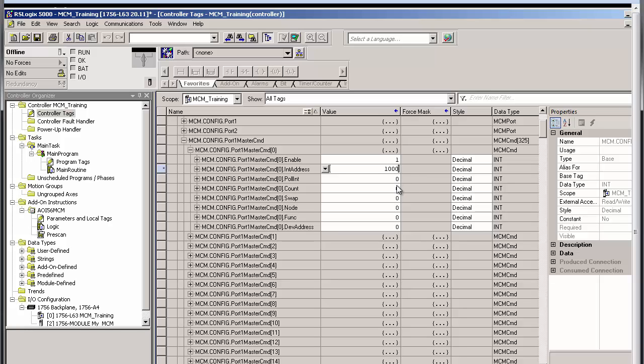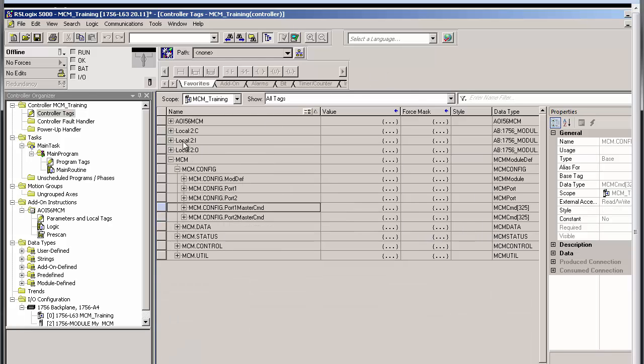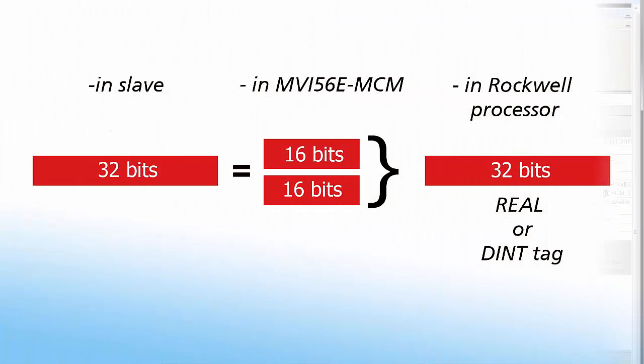Each of the two numbers I'm going to read will be float values, which, due to the limitations of the Modbus protocol, require two 16-bit registers each. So, I'll move down to count and enter 4 as the number of registers I want to use. I'll select node 1 as the device to give the command to. A function code of 3 means to read multiple holding registers. And a device address of 1024 means we'll start reading registers from address 41025 in our power monitor, which is where the values for phase A voltage that I'm trying to read are kept.